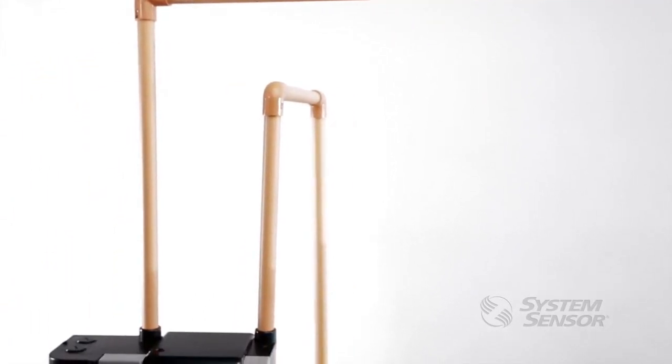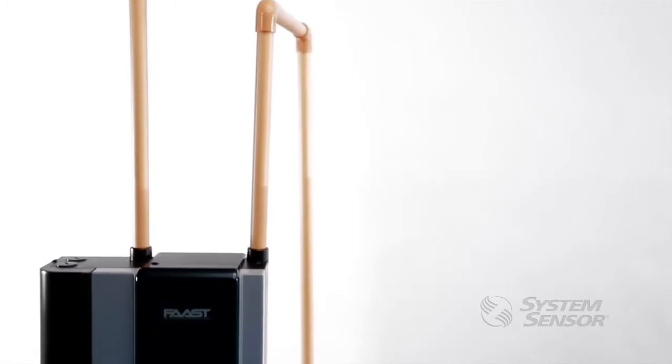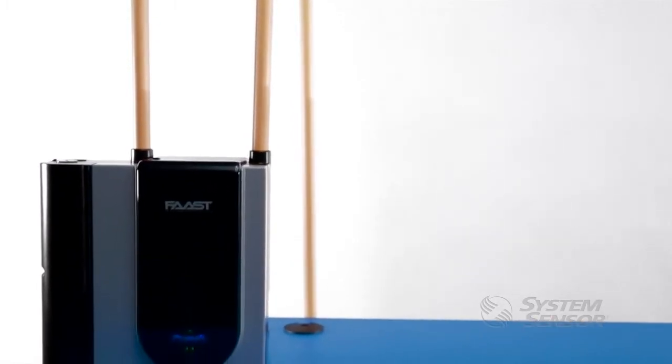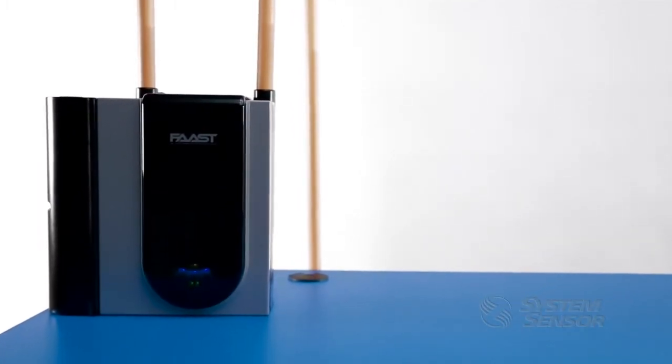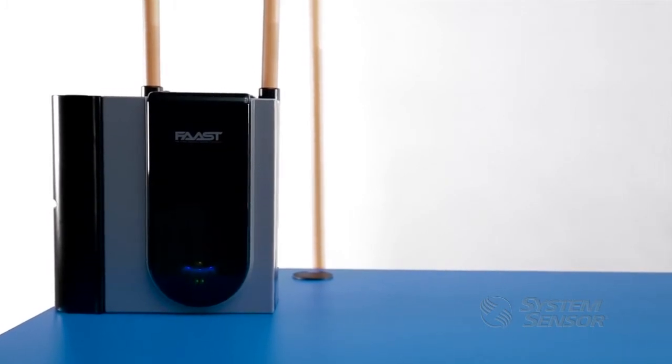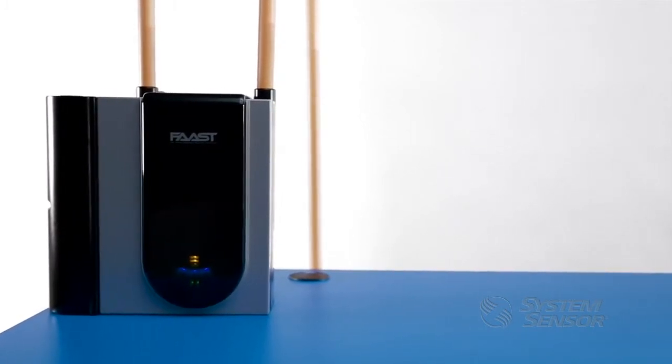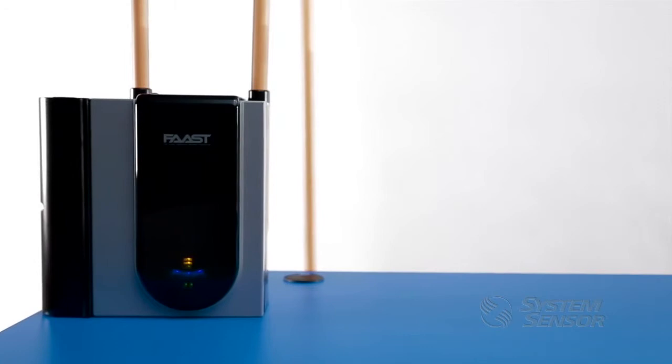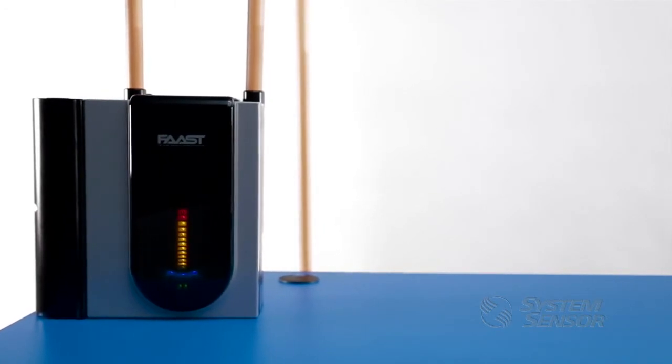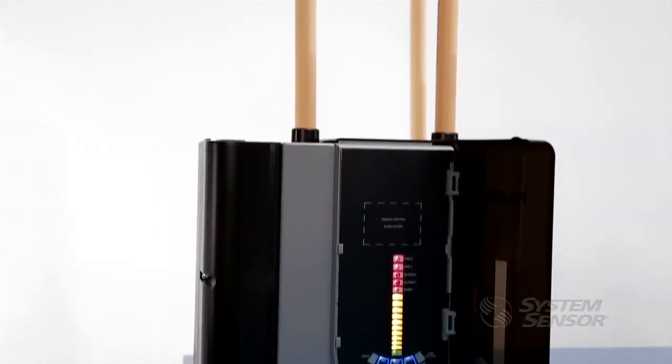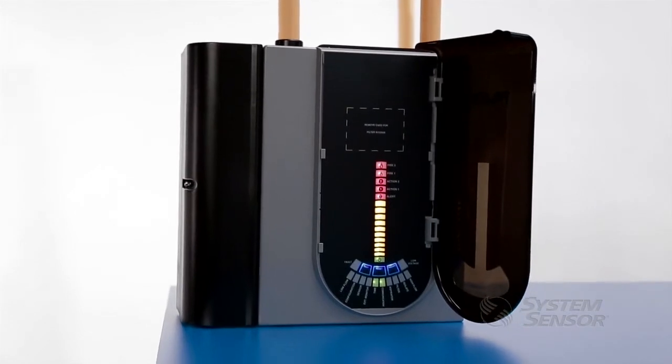Upon arriving in the detection chamber, dual vision technology bombards the sample with light from both the blue LED and the infrared laser. The signal from both sources is analyzed by advanced algorithms, confirming smoke and rejecting nuisance particles.